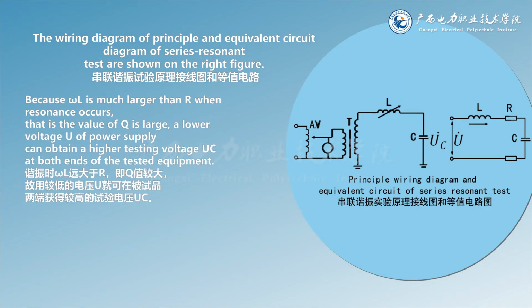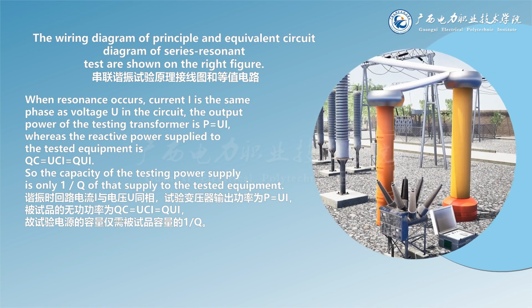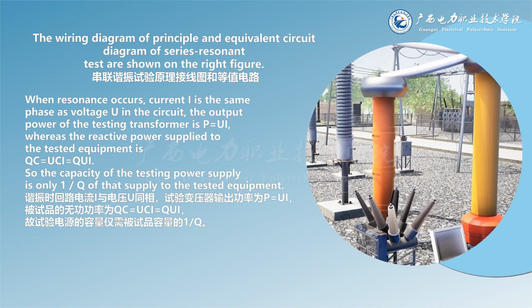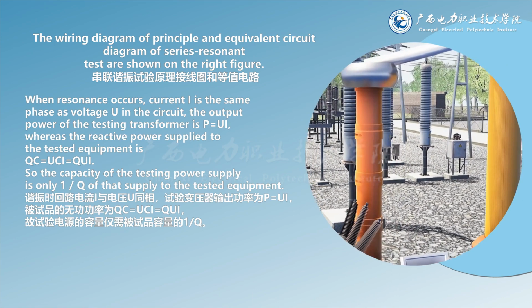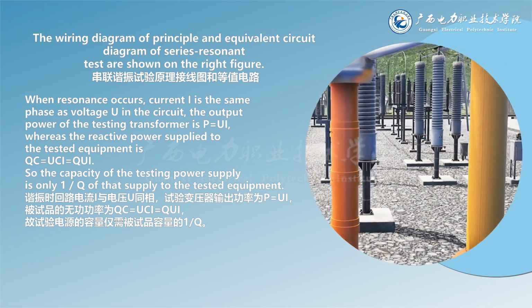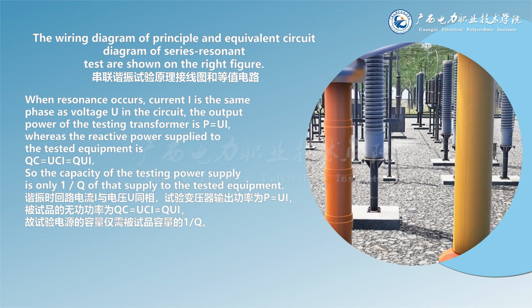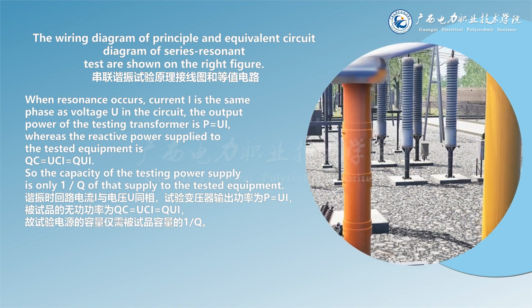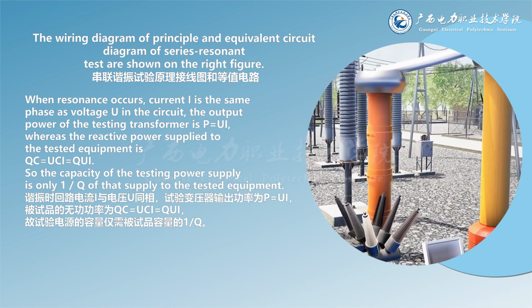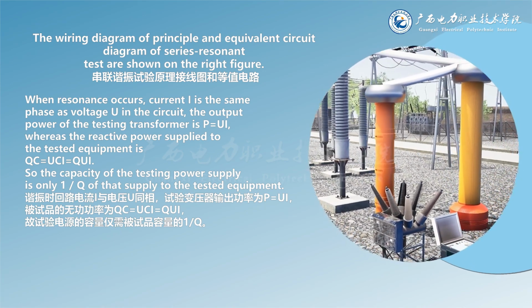Because omega L is much larger than R when resonance occurs, that is, the value of Q is large, a lower voltage U from the power supply can obtain a higher testing voltage at both ends of the tested equipment. When resonance occurs, current I is in the same phase as voltage U in the circuit, and the output power of the testing transformer is P equals UI, whereas the reactive power supplied to the tested equipment is QC equals UCI equals QUI. So the capacity of the testing power supply is only 1/Q of that supplied to the tested equipment.